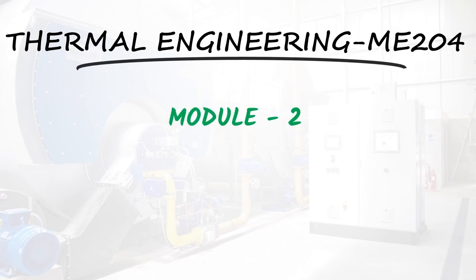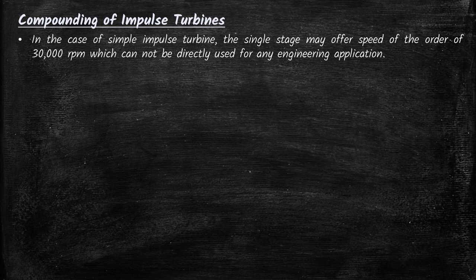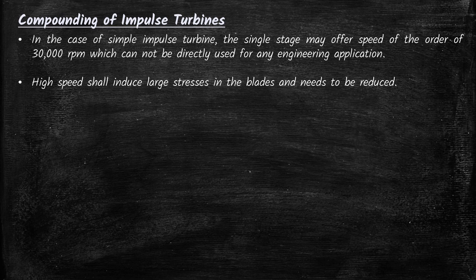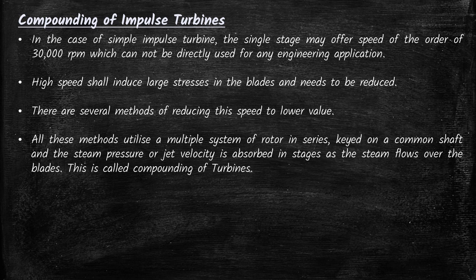Welcome back to the next lecture of thermal engineering. Today we will discuss from the second module the compounding of impulse turbines. In the case of a simple impulse turbine, a single stage may offer a speed of the order of 30,000 RPM, which cannot be directly used for any engineering applications. High speed induces large stresses in the blades and needs to be reduced. There are several methods of reducing the speed, all utilizing a multiple system of rotors in series keyed on a common shaft, where the steam pressure or jet velocity is absorbed in stages.